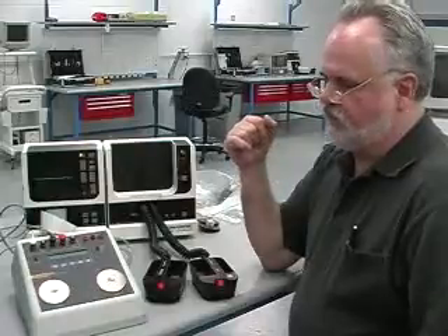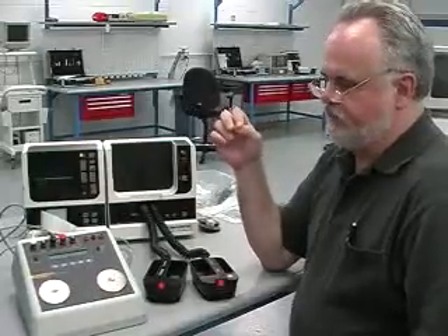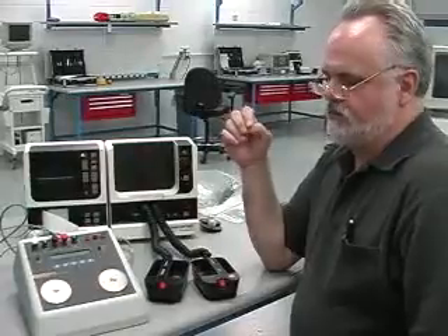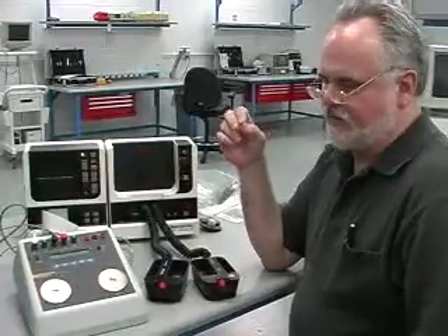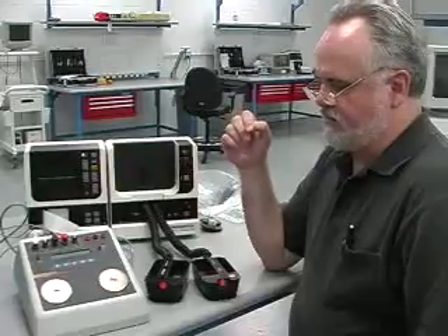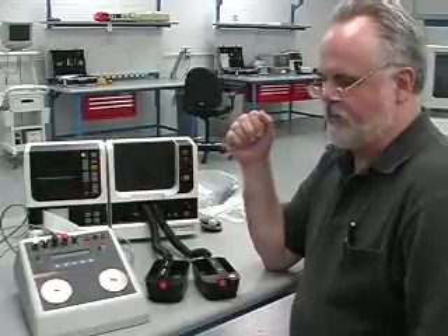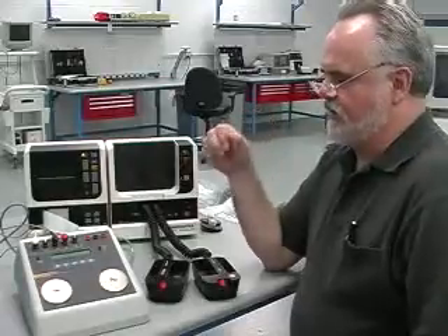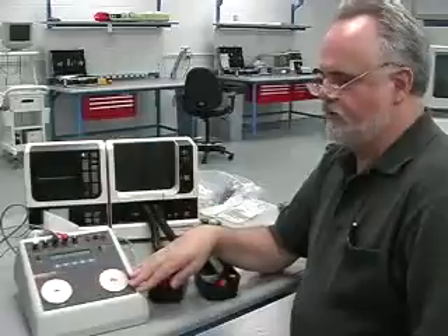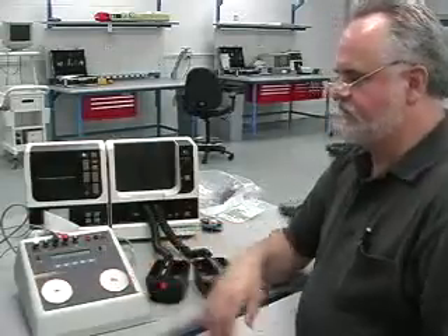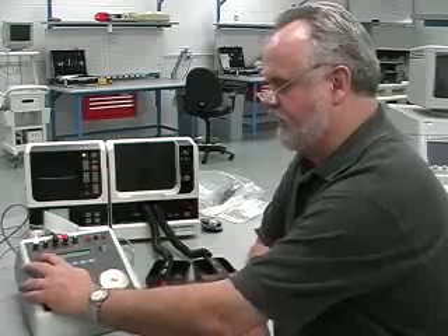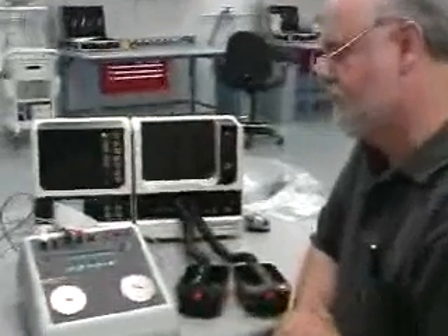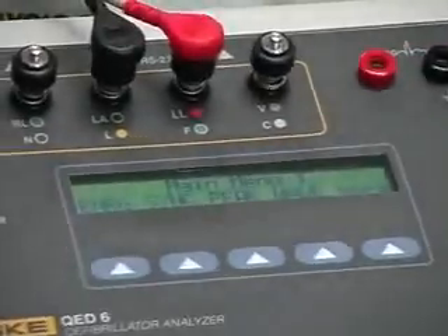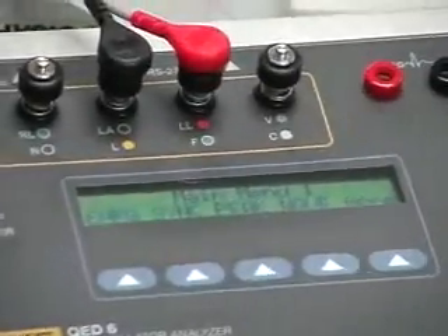plus the auto sequencing capability, and the QED6H, which has all M features and adds the ability to do transcutaneous pacemaker testing also. Basically all of those are identical in look, and you can discover which one it is primarily by looking at the menu. As it says, this is the 6H version, so this has the basic pacer testing capability too, in addition to the defibrillator testing ability.